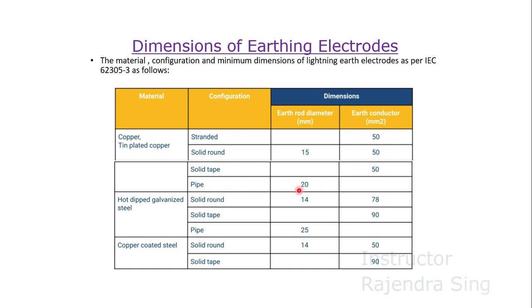If it is a pipe configuration, the earth rod diameter would be 20 mm. For HDG steel: if the configuration is solid round, the earth rod diameter would be 14 mm and the earth conductor would be 78 square mm. For solid tape, the earth conductor shall be 90 square mm. For pipe configuration, 25 mm would be the earth rod diameter requirement.